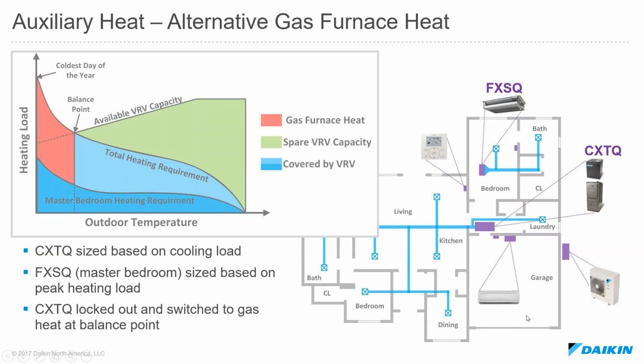Now, you may have noticed I've thrown an indoor unit in the garage and didn't really mention anything as far as sizing of that within the system, and that's just one benefit we have within these systems. We can throw these secondary sources where heating and cooling isn't critical and it doesn't really impact the sizing of the system, provided you have the additional connection capacity or connection index available to add that into the system. You don't necessarily have to size your outdoor unit to meet the load within that space, but we can still have the option of tempering that air for those non-critical days.